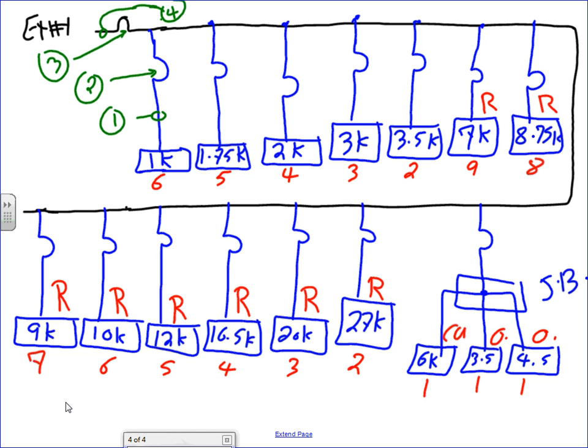I need somebody with a nice calculator that gives answers. Number 4. Nice stuff. So I'm going to start with the branch circuit and overcurrent device for all these pieces of equipment. By the way, Ashley, I said I have 6 of these. I'm not putting them on the same branch circuits. I actually have 6 branch circuits here, 5 branch circuits here. Does that make sense? I'm not grouping them. I'm having a branch circuit for each one of them. The only time I group on one branch circuit is this right here. Cool? Just to give you an idea. All these numbers are single branch circuits. So there's a lot of branch circuits coming out of this system.